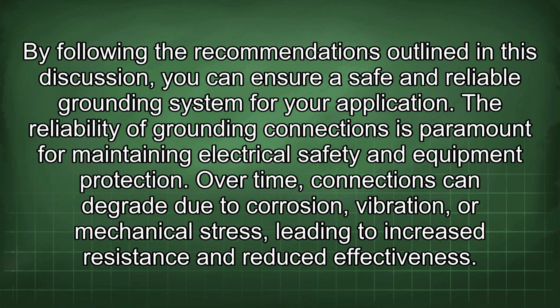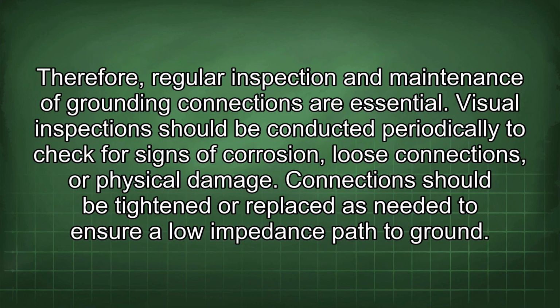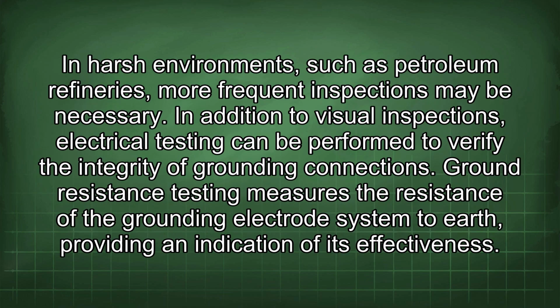Over time, connections can degrade due to corrosion, vibration, or mechanical stress, leading to increased resistance and reduced effectiveness. Therefore, regular inspection and maintenance of grounding connections are essential. Visual inspections should be conducted periodically to check for signs of corrosion, loose connections, or physical damage. Connections should be tightened or replaced as needed to ensure a low impedance path to ground. In harsh environments, such as petroleum refineries, more frequent inspections may be necessary.